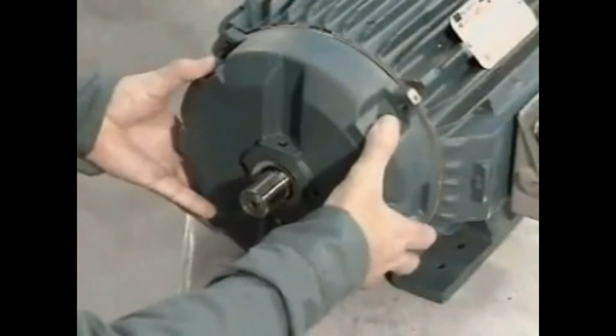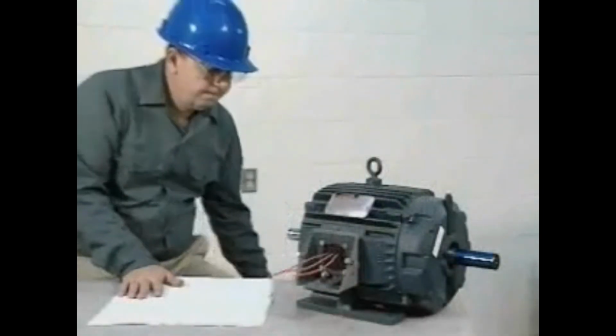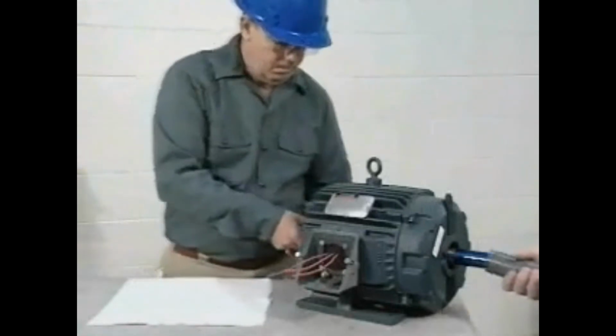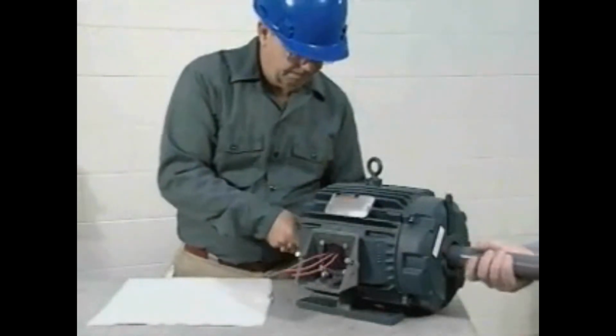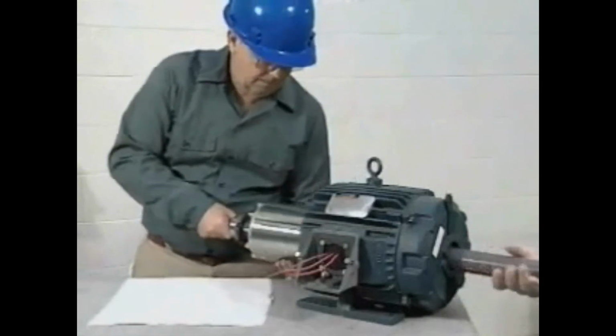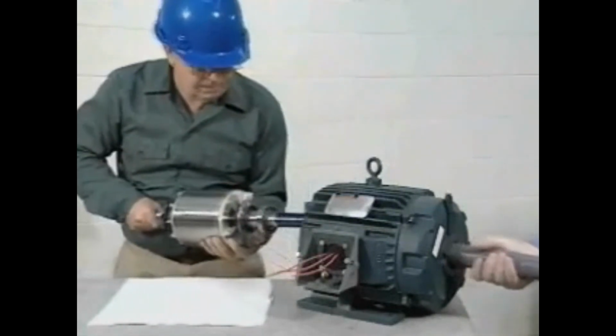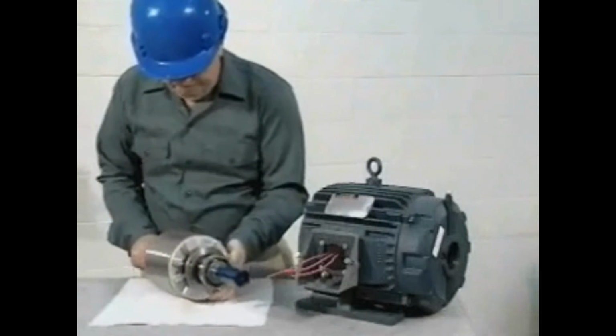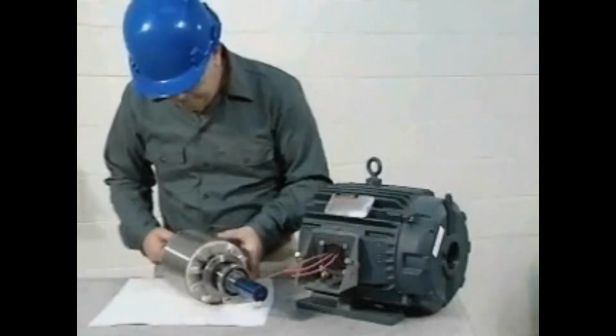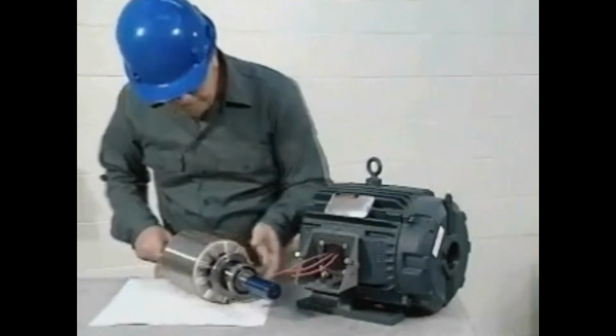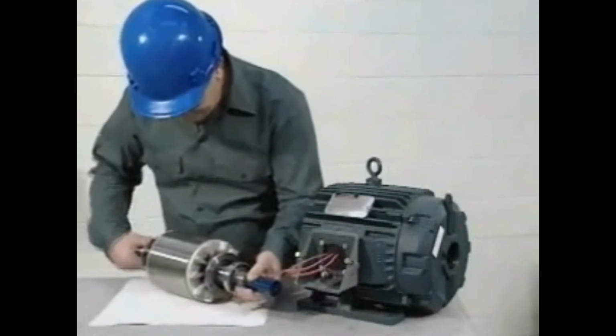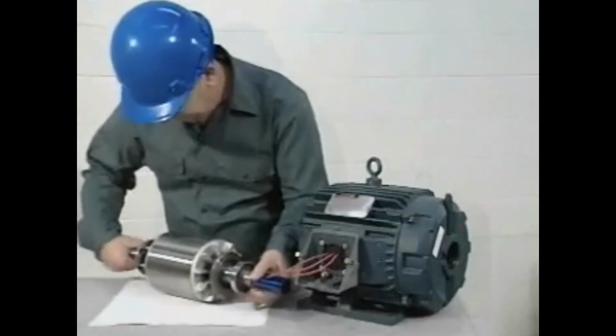Remove one end bell. Use a piece of wood or rubber mallet to help set it free. As you remove the end bell, take care so the rotor does not drop and damage the stator. Rotor removal is a very precise operation. It may take 2 people to do it. Make sure the clearance between the rotor and the stator is even on all sides and at both ends. The rotor must be properly aligned to prevent damage to the rotor or the stator windings as the rotor is removed. Set the rotor aside on a clean, soft surface where it will not be damaged or roll.